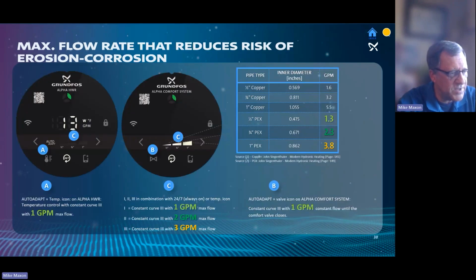flows. Like I said, they want 2 feet per second, and that does change for copper and PEX. We have erred on the slower side because we know it'll still work, and we have erred at 1 gallon a minute, 2 gallons a minute, 3 gallons a minute for the different size pipes. But the actual calculations are 1.3, 2.3, and 3.8. Again, if you do the guided setup, it'll ask you what size pipe it is and what kind of pipe. And so you could actually, through the guided setup, set it for the 1.3 or the 1.6 if it's copper.